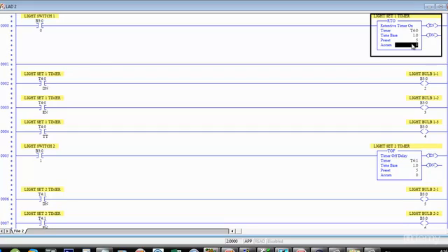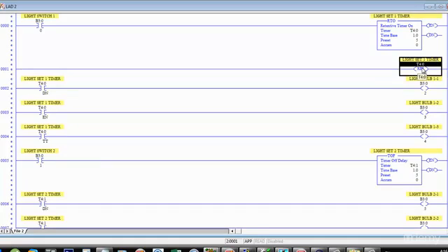So when I turn it on again for another 2 seconds and then turn it off, now my accumulator adds those 2 seconds to the previous second that it was on. Now my timer is up to 3, which means once I turn my light switch on again for 2 seconds, this timer is going to time out, and it will retain that time until I use a reset command on T40.